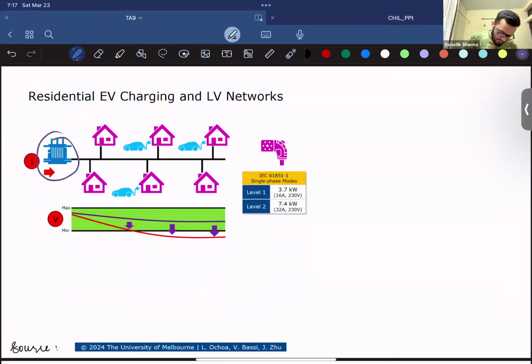So what happens is, let's say you have a head of feeder transformer connected to a LV network, a low voltage network, usually 230 volts AC, 50 hertz. If you all have EVs at your residential places on this low voltage network, when you connect to your power socket, the voltage - since it's a function of the current being drawn at your premises - tends to sag at the bottom of the feeder. At the head of the feeder, the voltage is at its nominal level, but as it approaches the end of the feeder, the voltage starts sagging.